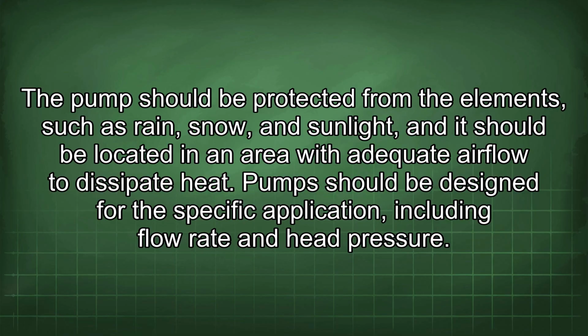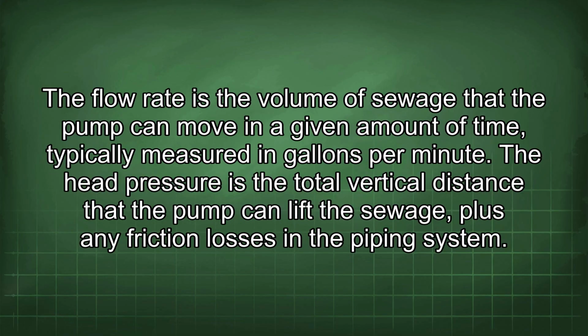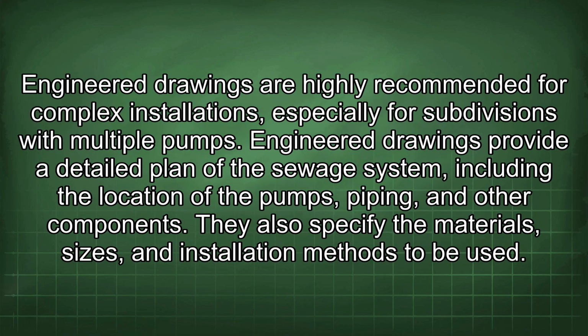Pumps should be designed for the specific application, including flow rate and head pressure. The flow rate is the volume of sewage that the pump can move in a given amount of time, typically measured in gallons per minute. The head pressure is the total vertical distance that the pump can lift the sewage, plus any friction losses in the piping system. Engineered drawings are highly recommended for complex installations, especially for subdivisions with multiple pumps. Engineered drawings provide a detailed plan of the sewage system, including the location of the pumps, piping, and other components. They also specify the materials, sizes, and installation methods to be used.